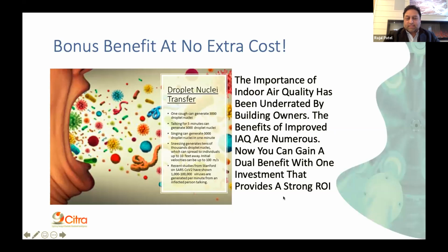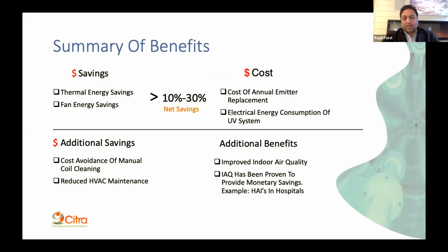That's a great dual benefit there. To sum things up, on the savings side, the savings are happening from thermal energy savings, which also result in fan energy savings. And then on the cost side against that, you have annual replacement of the emitters, and the actual energy consumed by the UV system itself. So we have a net savings of 10 to around 30%.